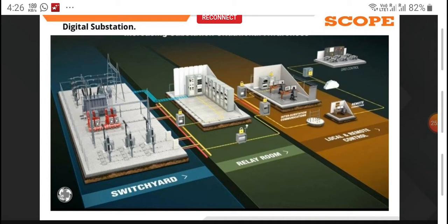Digital substation means there is a difference from what people say about it. Digital substation means that everything, from the CT, PT or breaker to the control room, is digital. Not a single copper cable is laid for this signal-carrying purpose. So that is the complete digital substation. I'm going to explain what a digital substation is and what the things in a digital substation are.